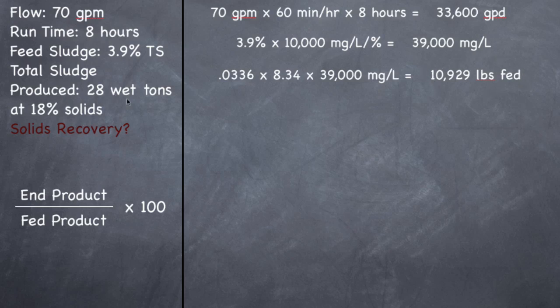What we produced was 28 wet tons — it's not dry yet. You can almost never get a belt press 100% dry without some sort of oven attached to it. So we've figured out how much we fed; now we need to find the end product. We produced 28 wet tons and it's 18% solids, meaning it's 82% wet.